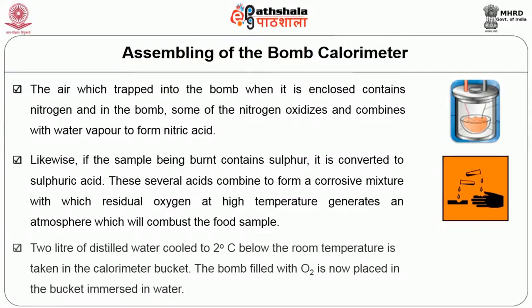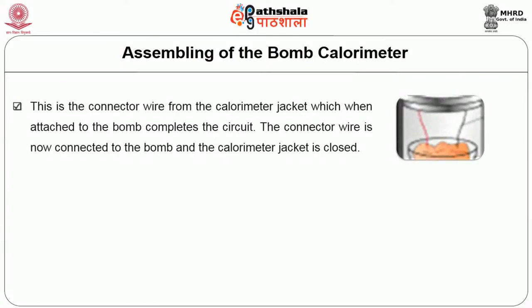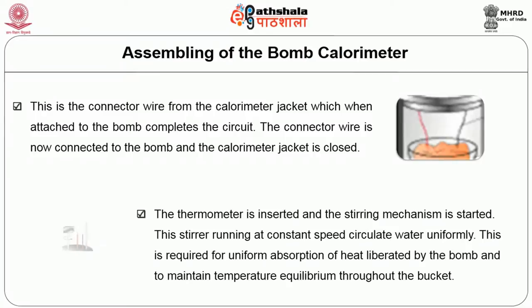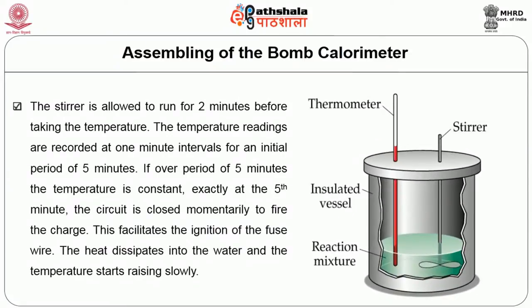2 liters of distilled water cooled to 2 degrees Celsius below room temperature is taken in the calorimeter bucket. The bomb filled with oxygen is placed in the bucket immersed in water. The connector wire from the calorimeter jacket is attached to the bomb to complete the circuit, and the calorimeter jacket is closed. The thermometer is inserted and the stirring mechanism is started, running at constant speed to circulate water uniformly, ensuring uniform absorption of heat and temperature equilibrium. The stirrer is allowed to run for 2 minutes before taking the temperature.